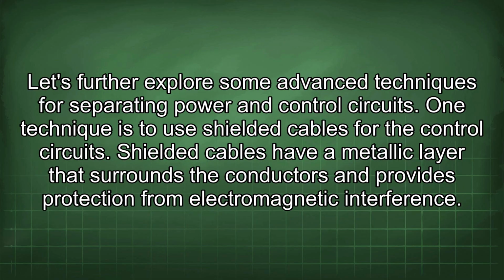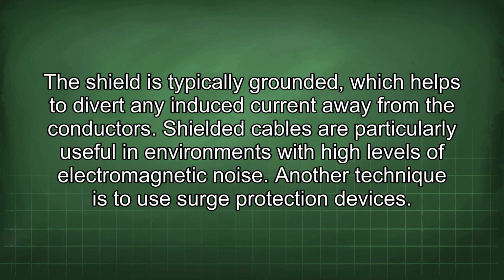Let's further explore some advanced techniques for separating power and control circuits. One technique is to use shielded cables for the control circuits. Shielded cables have a metallic layer that surrounds the conductors and provides protection from electromagnetic interference. The shield is typically grounded, which helps to divert any induced current away from the conductors. Shielded cables are particularly useful in environments with high levels of electromagnetic noise.